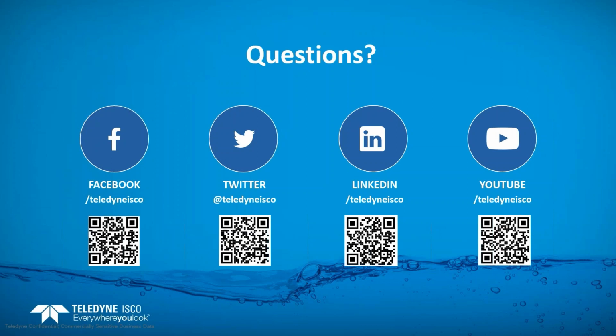Okay, we got one here. How does the AV sensor measure area if it is not mounted directly under the flow? Well, as far as the AV sensor, it would need to be underwater for it to actually measure any area for the flow. So I believe maybe we're talking about the surcharge sensor on the laser, where it is actually mounted out of the water. How that works is that the laser will operate up until the water rises and hits that surcharge sensor. Once the surcharge sensor is underwater, it's going to click on and start measuring area versus the laser trying to measure.